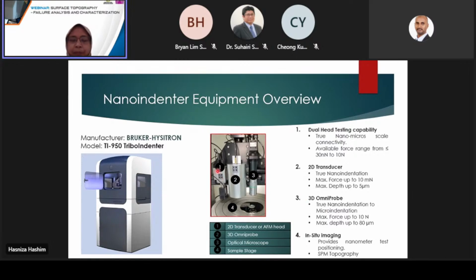For this 2D transducer, the probe can also be used as a contact mode scanning probe microscope, or SPM. There are piezo actuators which can scan the probe at a low force of around 2 micronewtons along the surface, rastering and measuring the displacement of the probe constantly. From that, it can give you a spatial representation and a 3D value. So basically you get a topographical map of the area that you want to scan. The SPM method is very important for many users as it can help get an approximate value of the roughness of the sample surface before we do the indentations. It can also aid in selecting a very specific area for testing, and it can help by imaging the residual indent to confirm or even quantify its quality. The system also comes with a pretty good optical microscope, which is mostly used to navigate the sample.